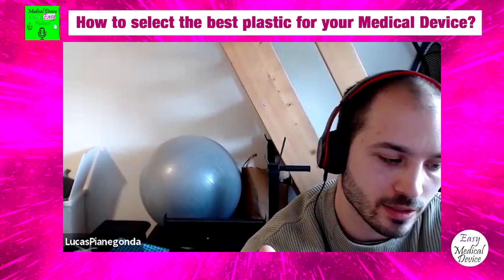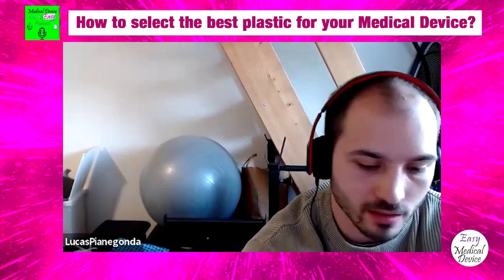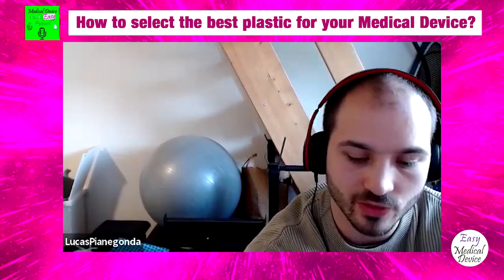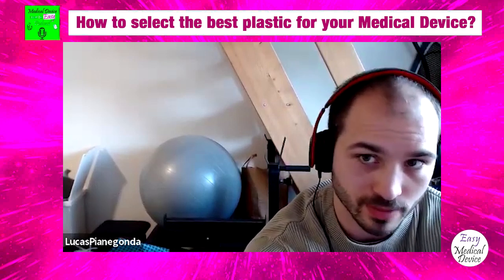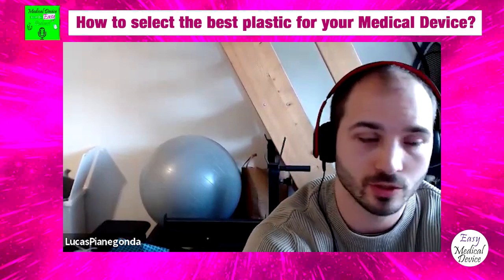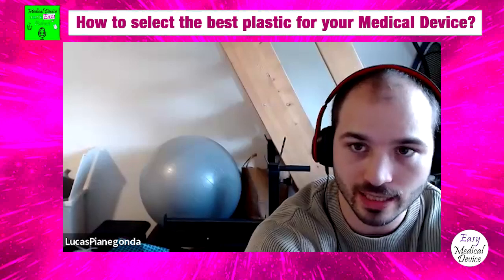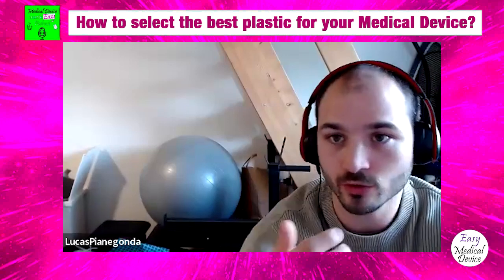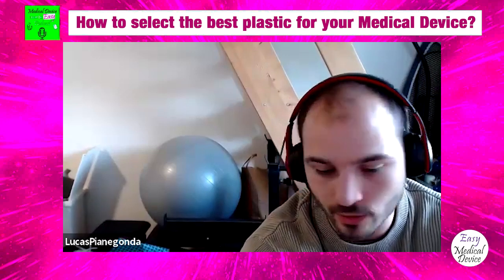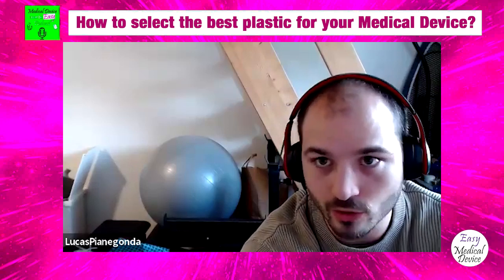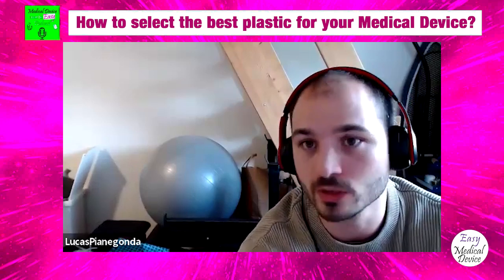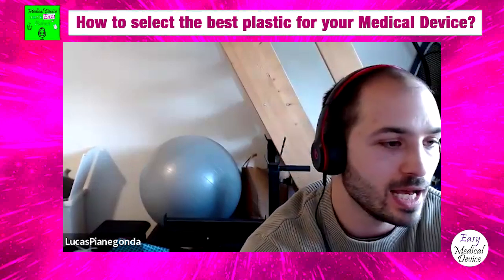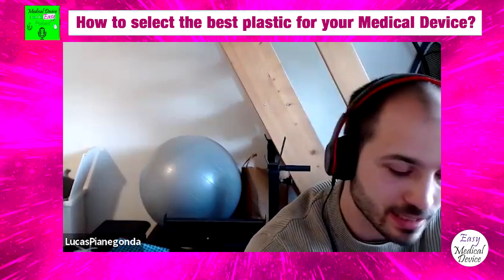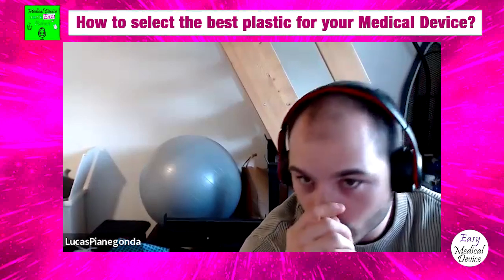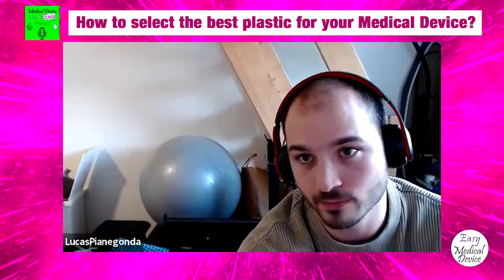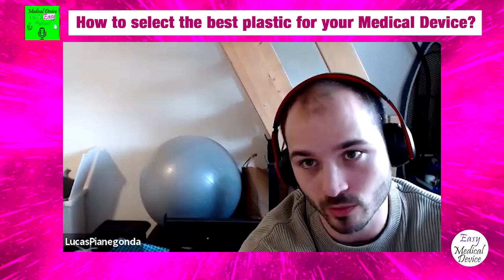But from an MDR or from an FDA perspective, you are not obliged to use a medical grade plastic. There is no forcing you to use that. You could also use a so-called food grade, which is okay for food contact. It has no substances of concern in it because you wouldn't use it with food otherwise. It can be okay. It depends on the risk class. I mean, with a food grade, they can change the additives as they want to, and they won't tell you.